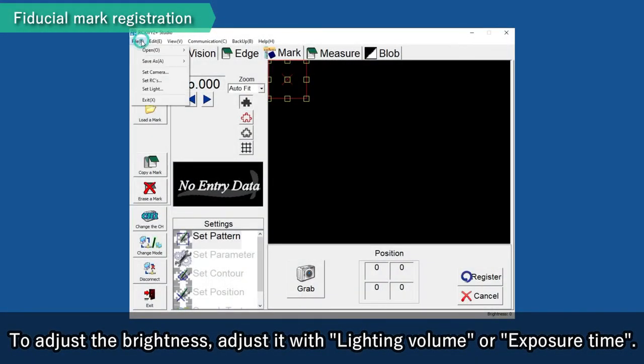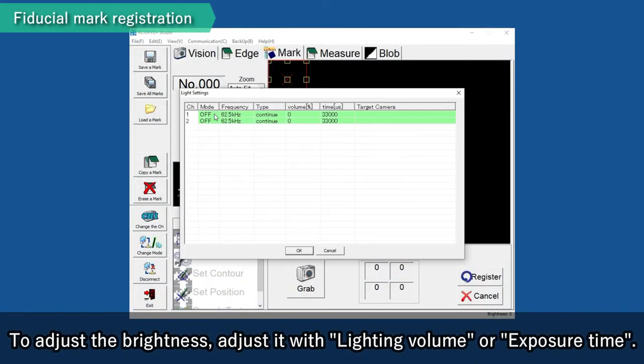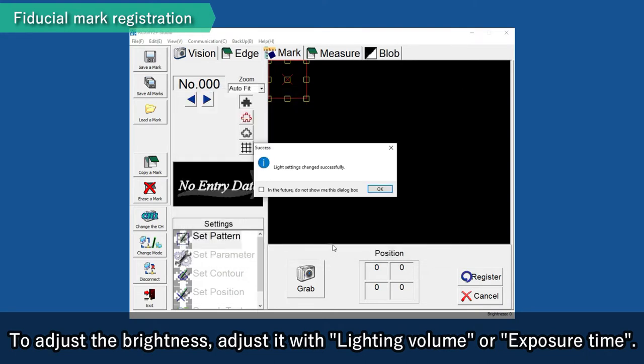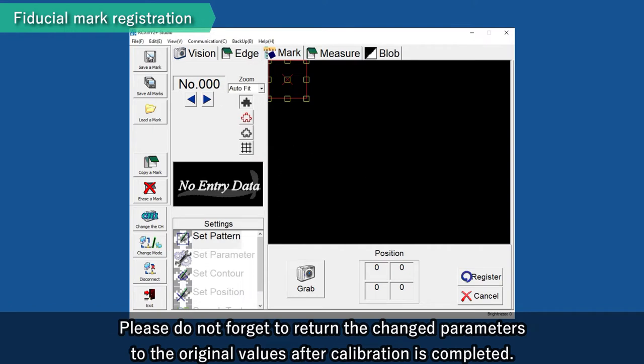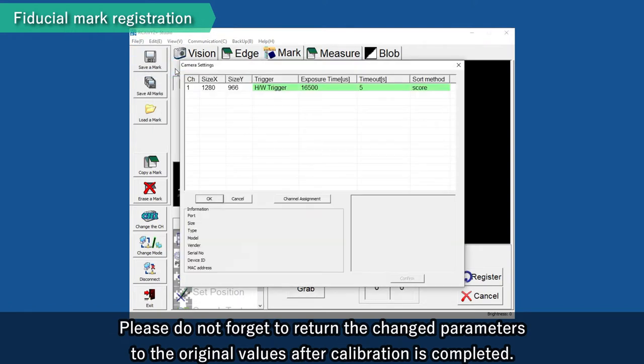Do not touch the focus or diaphragm of the lens that was adjusted for the actual workpiece. To adjust brightness, adjust it with lighting volume or exposure time. Please do not forget to return the changed parameters to the original values after calibration is completed.